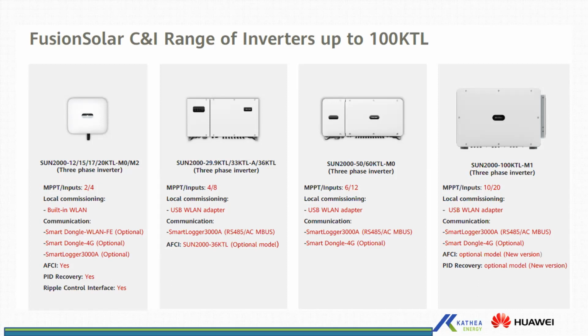So HUAWEI inverters have a built-in function to keep that process in check in the commercial and industrial. That is the built-in PID recovery. So the PID that occurs during the day, at night the system would actually try and recover those cells such that the panels will keep working at their optimal rating. However, you have to activate it on the application during commissioning. We'll also touch base on that tomorrow on our commissioning webinar.